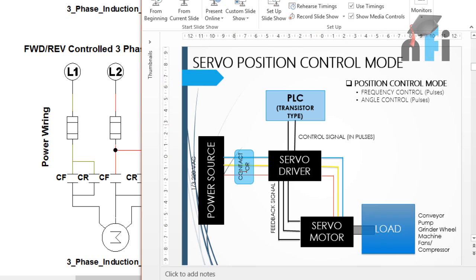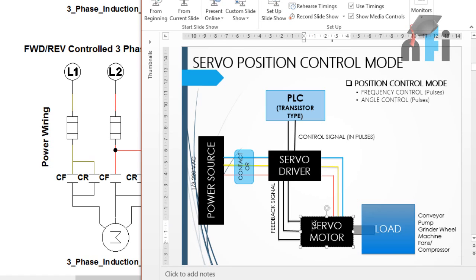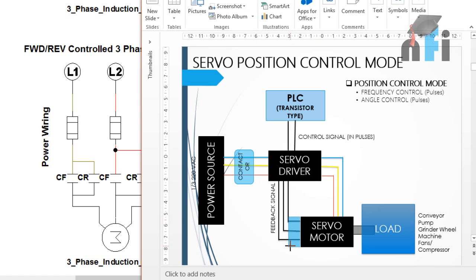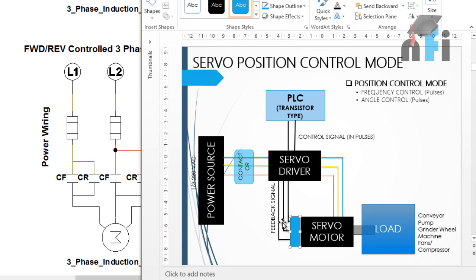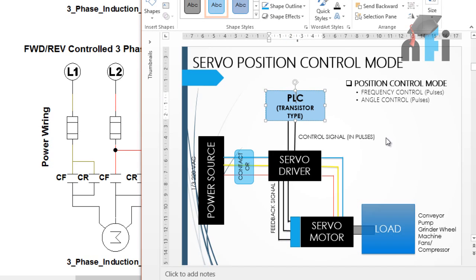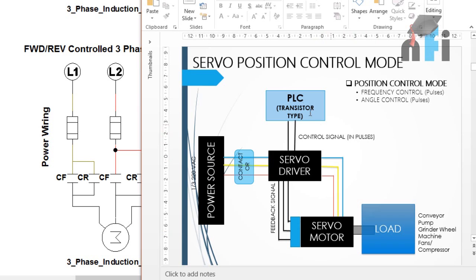In servo position control mode, the basic layout involves a servo driver, which is analogous to a VFD in induction motor control. The driver gives an AC signal to the servo motor. At the back of the motor there is an encoder, which gives feedback to the servo driver about its position and RPM. The driver can read this feedback and display it on a monitor. If you want to display feedback on an HMI or control the motor using a PLC, you need to install a PLC.